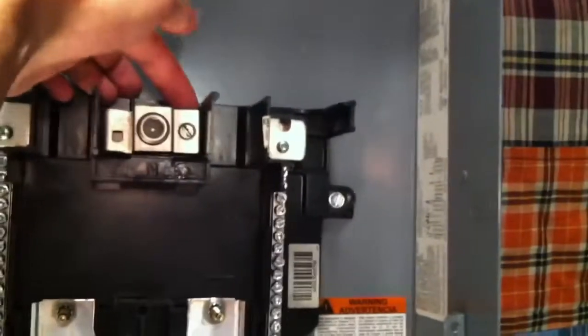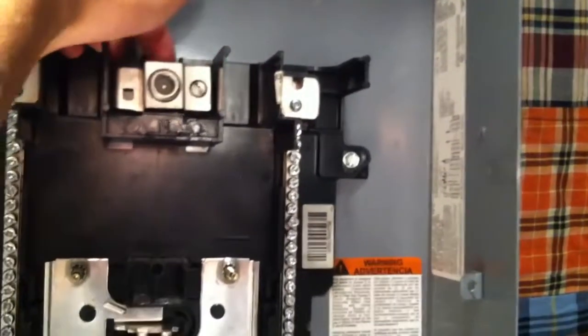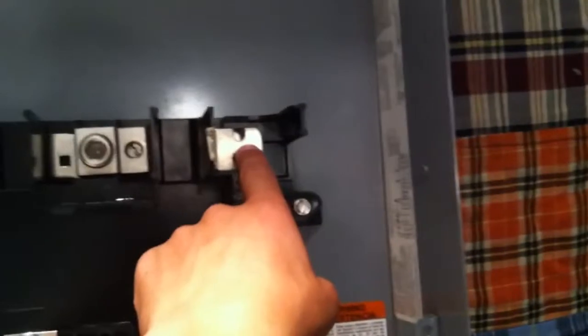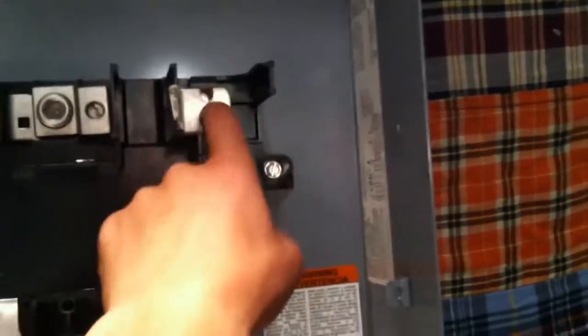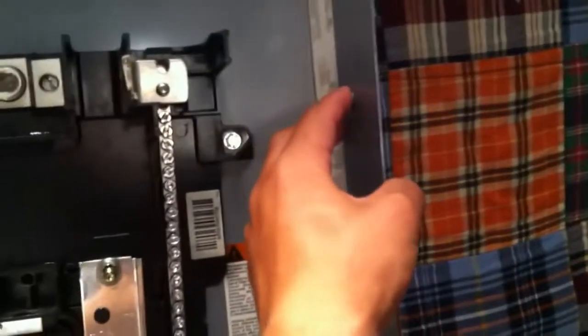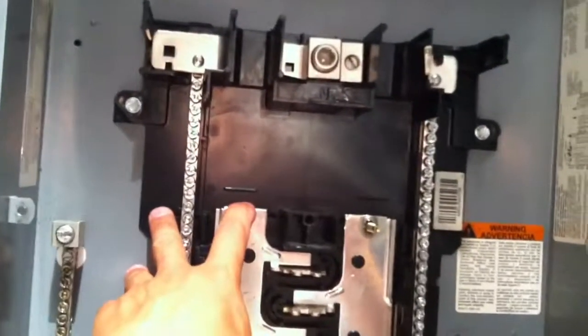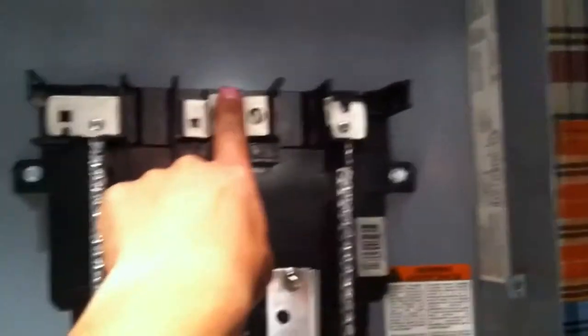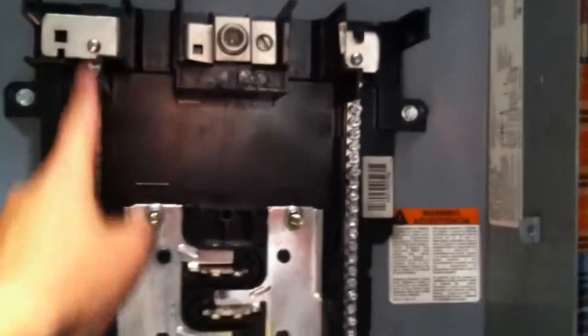If this is a main panel, you're going to have your ground wire going in there, you're going to have your neutral going in there, so the same thing, and you're going to have a screw that goes in through there, and it's going to actually tie this neutral and ground, which are together, to the case of this to make this case grounded. In this case, I was using it as a sub panel, which means all the neutrals are floating, okay? None of them are touching the ground. So I didn't have that screw going there.